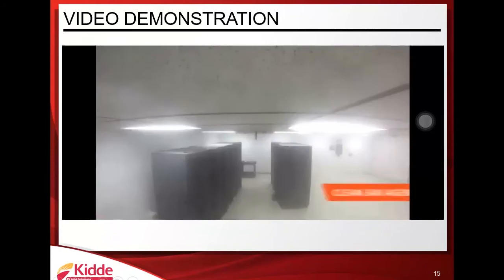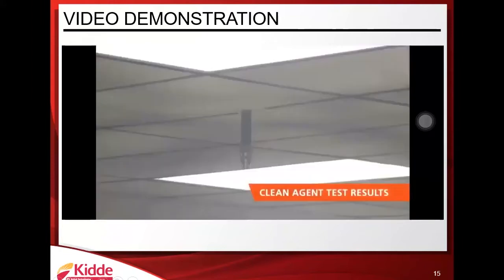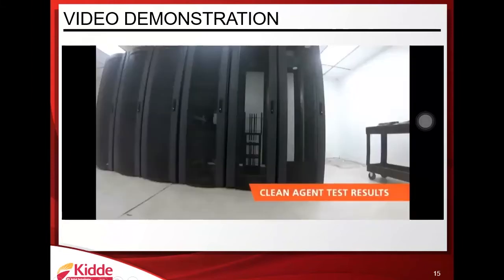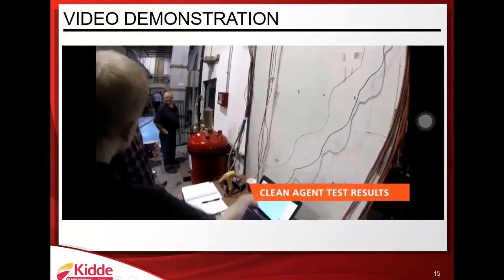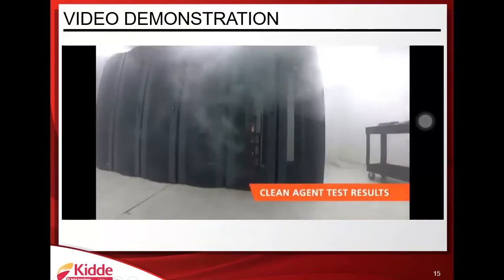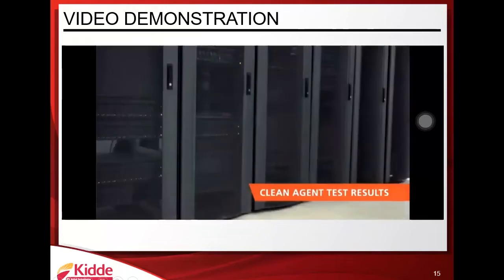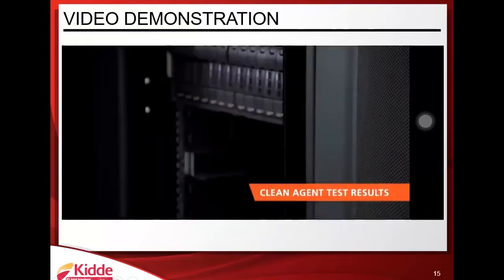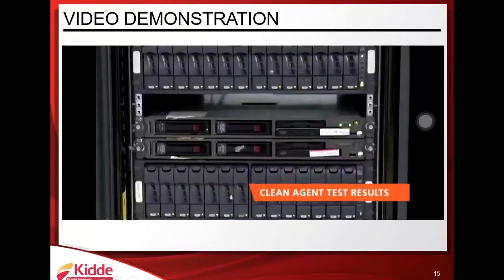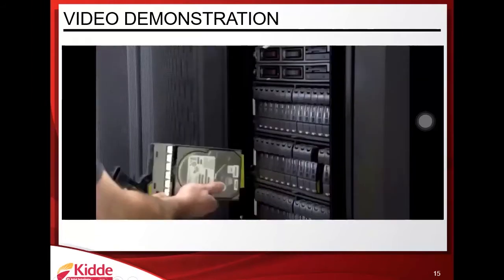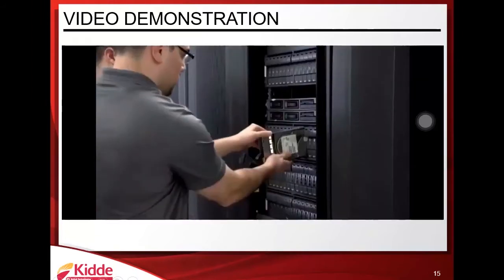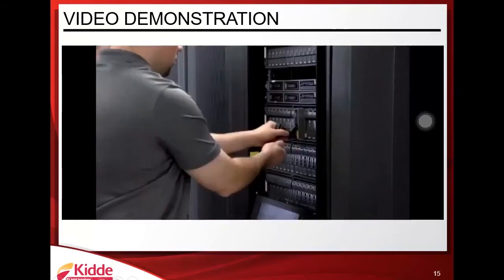The results of the Kidde Clean Agent System test are dramatically different. Even though the cabinet temperature reached 230 degrees Fahrenheit before the agent discharged, the room and servers show virtually no sign of damage. From the perspective of IT operations and data security, it's as if the fire in the data center never happened.